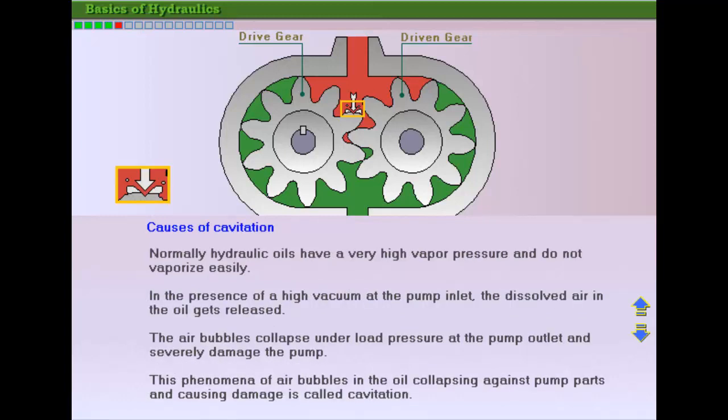Normally, hydraulic oils have a very high vapor pressure and do not vaporize easily. However, there is still a chance of cavitation as the dissolved air in the oil, typically 6-10%, is released in vacuum conditions at the pump inlet.